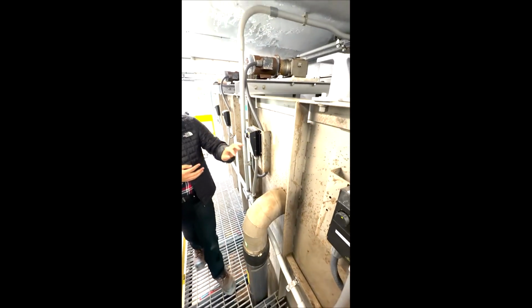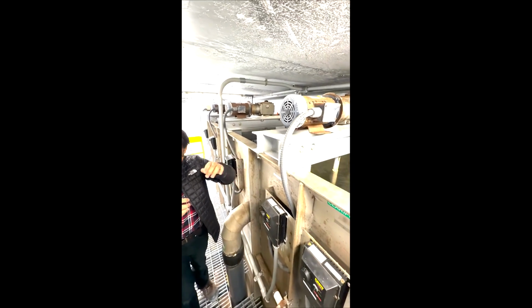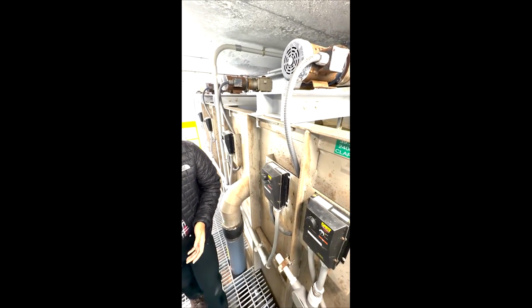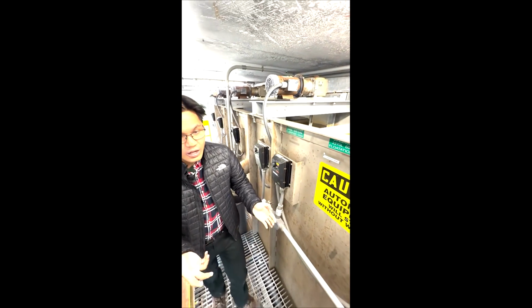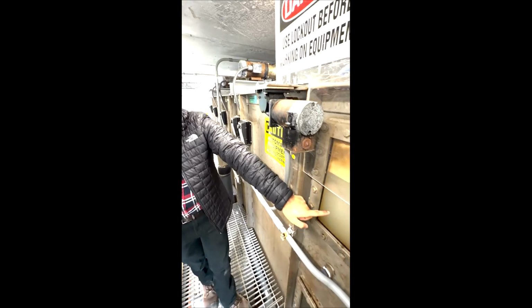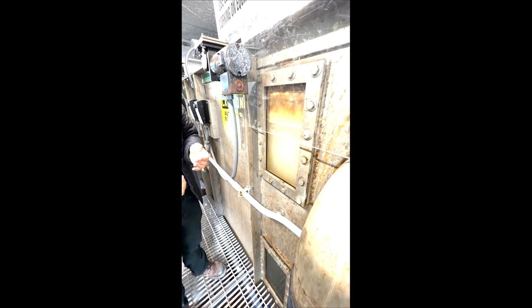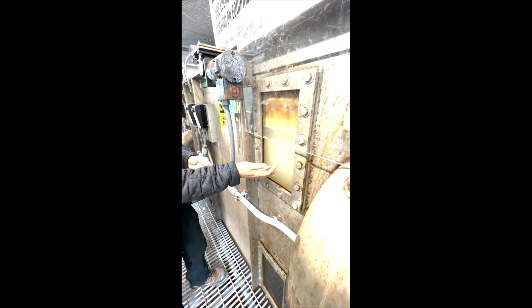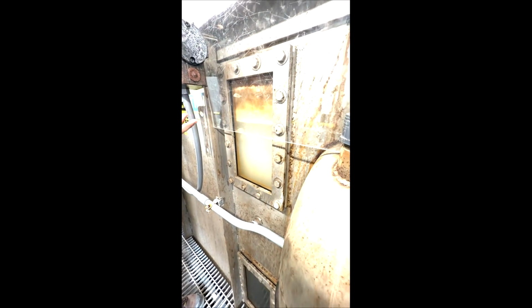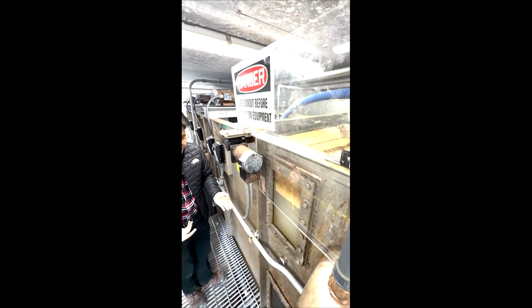This is floc tank 2, and this is just a tank with no mixing to allow things to fall to the bottom. So what exactly is a floc? You can see over here these white particles. These are what's formed when we add that chemical. These white particles are rising to the surface so that they can eventually be scraped off using this paddle and removed from the town's water system.